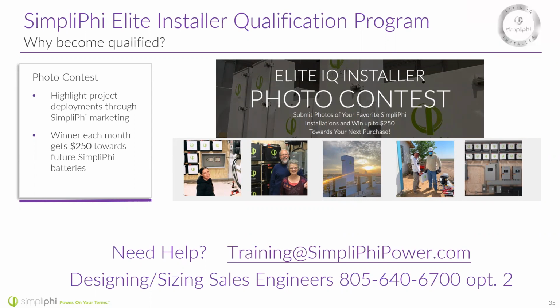Regarding that 20 kilowatt hour standard, one thing we like to point out is that our new ESS has a 4.9 kilowatt hour battery, which is great because you could stack four of them and be just under that 20 kilowatt hour limit that we're seeing some AHJs implement. Los Angeles County, for example, doesn't necessarily follow NFPA—they have their own standards, and they're saying 20 kilowatt hours. But what can happen, as Matthew asked about the 20 kilowatt hours through NFPA, is that certain jurisdictions will allow you to exceed that. There was a great SEIA (Solar Energy Industries Association) webinar on this, talking about how your UL certifications can supersede some of the requirements from NFPA 855, although you still have to adhere to some of those.